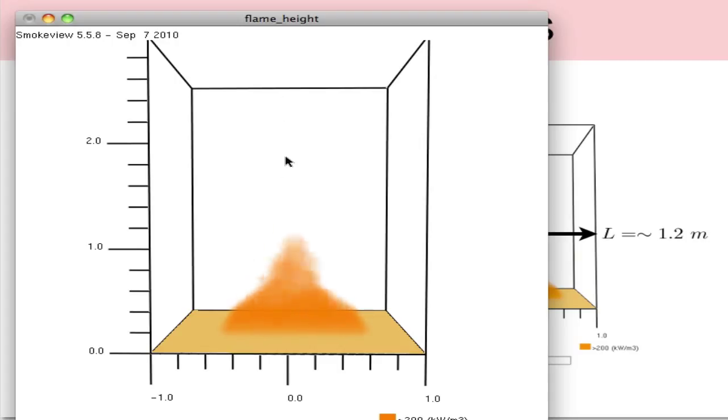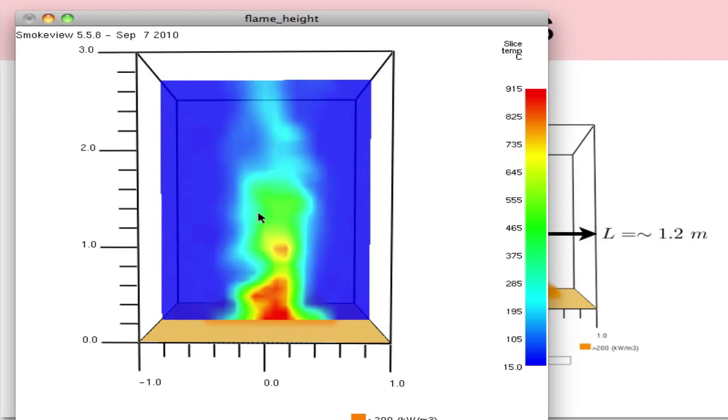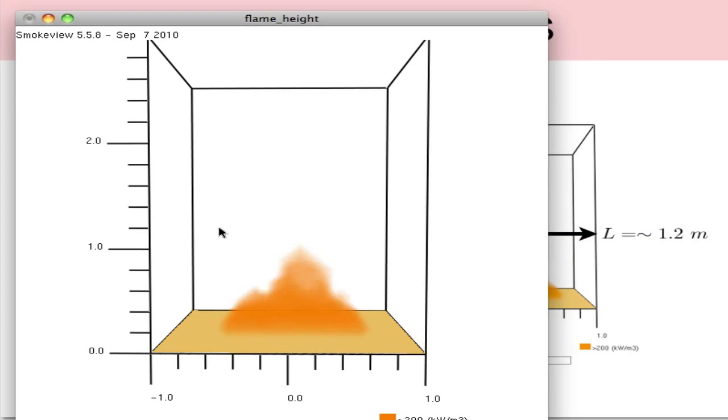If we look we can see the different regions. First we see the continuous flame region near the base, then here we see the intermittent flame region where the flame is sort of pulsing up and down and there's not always flame. Also above here if I turn on the temperature of the slice file, we can see hot gases exist above the physical flame height on the order of 400 to 500 degrees celsius, so that's defined as the plume region.